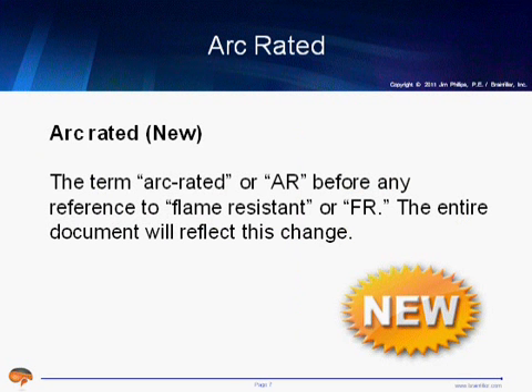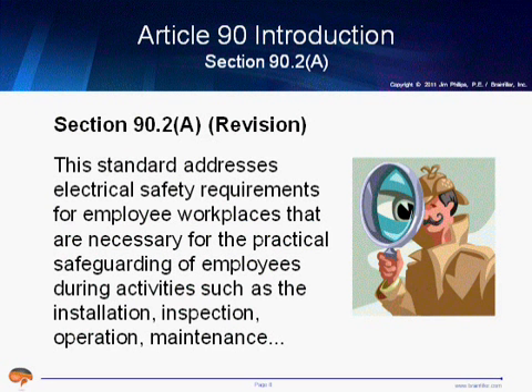Beginning with the 2012 edition, NFPA 70E is going to be changing the word flame resistant, FR, and begin using the terminology arc rated, or AR. And this is really just to be consistent with ASTM standards, because what you have is arc rated material. It is flame resistant, but flame resistant material is not necessarily arc rated. So that's a change that's going to keep us consistent with ASTM.